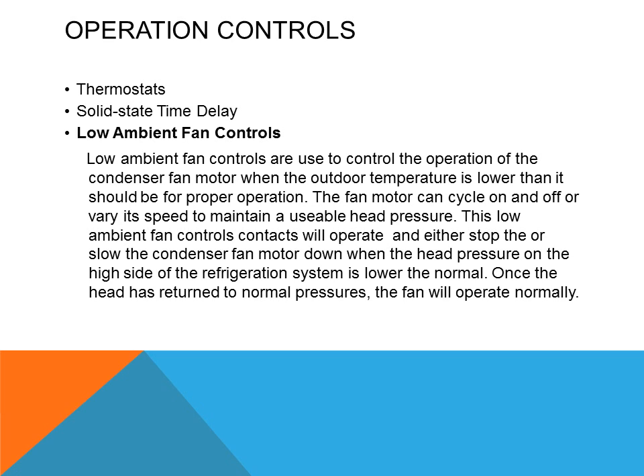Low ambient fan controls are used to control the operation of the condenser fan motor when the outdoor temperature is lower than normal for proper operation. The fan motor can cycle on and off or vary its speed to maintain a usable head pressure. When the head pressure on the high side of the refrigeration system is lower than normal, the control will stop or slow the condenser fan motor. Once head pressure returns to normal, the fan will operate normally.